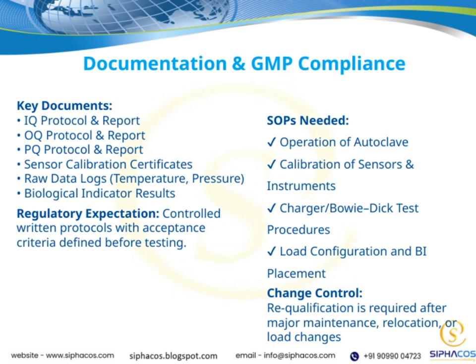First, we have the IQ protocol and report, which ensure that all equipment and systems are installed correctly and meet the required specifications. Then, the OQ protocol and report focus on verifying that the equipment operates as intended under controlled conditions. The PQ protocol and report go a step further, confirming that the process consistently produces the desired quality in real-world production settings. Additionally, calibration certificates for sensors are essential to demonstrate that our measurement devices are accurate and reliable. Raw data logs, including temperature and pressure readings, are maintained to provide traceability and support compliance. Biological indicator results are also critical, as they verify sterilization effectiveness through biological testing.